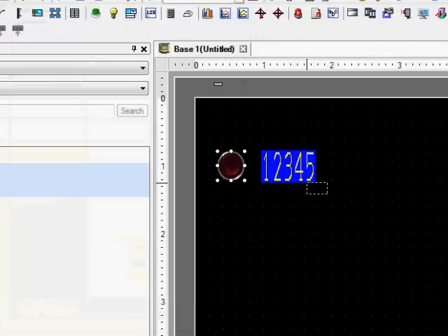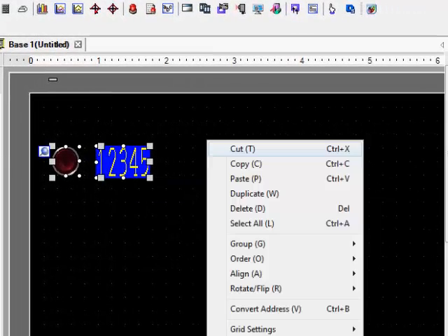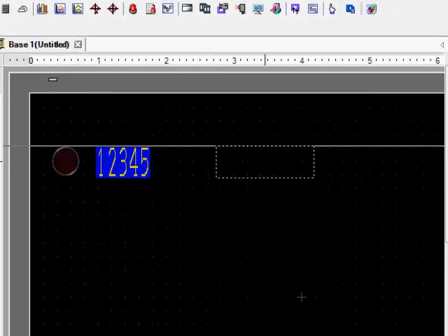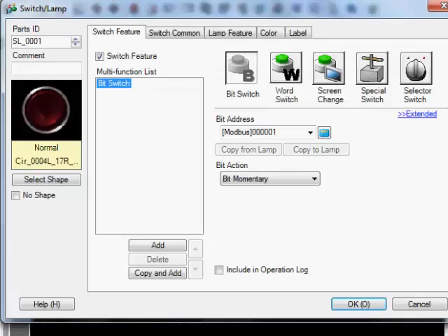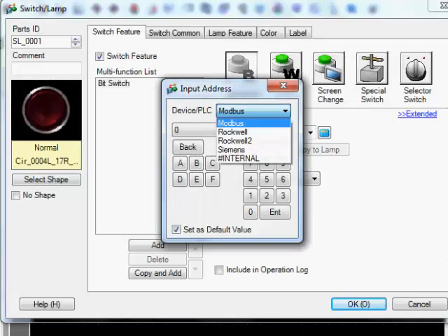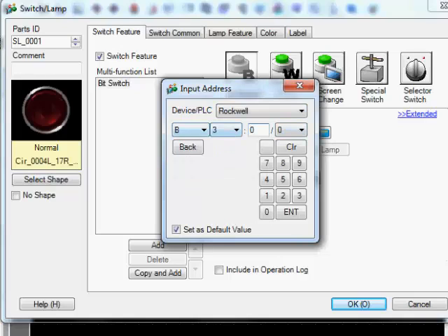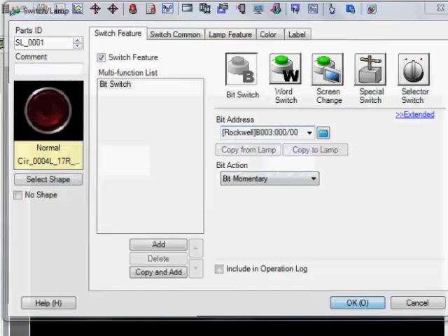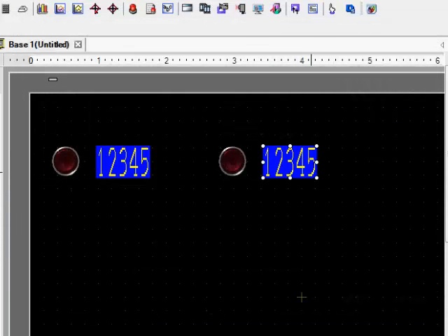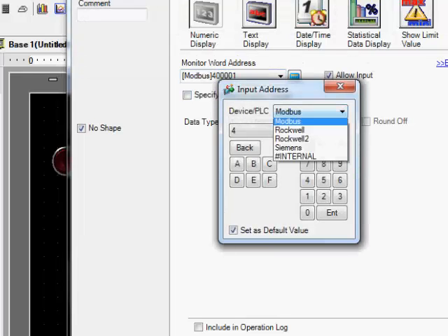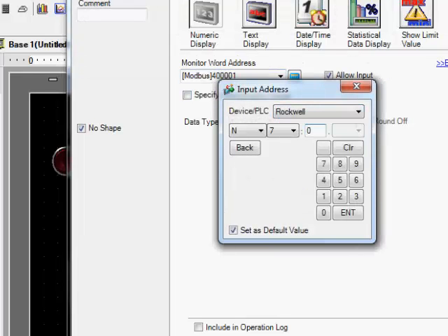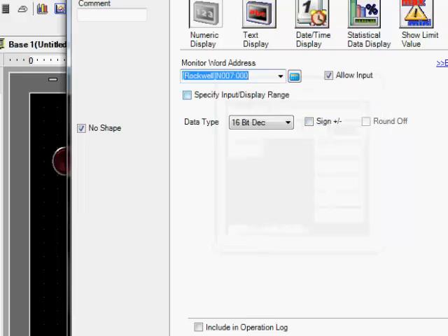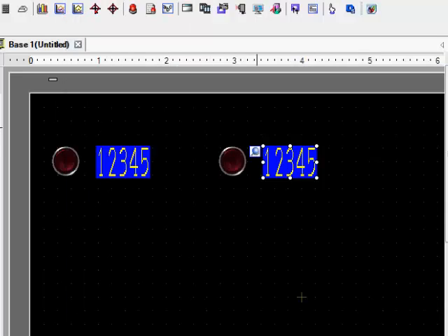Now if I wanted to go to another device we can just copy and paste this over. Go into each one of those, hit your calculator again, select Rockwell this time and maybe go to like something like B3:0/0. On our data display hit the calculator, select the Rockwell that you need, and then put its address in something like N7:0.